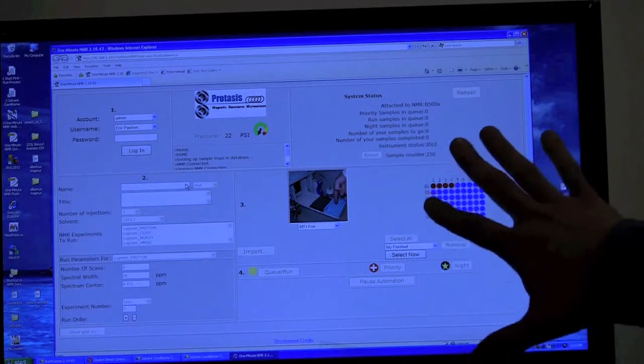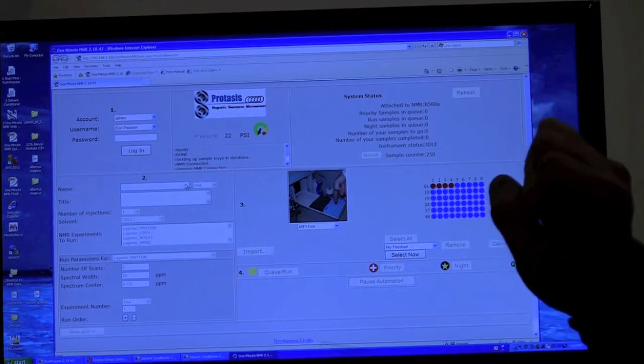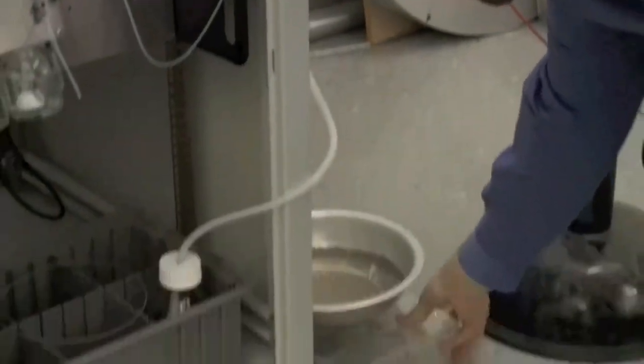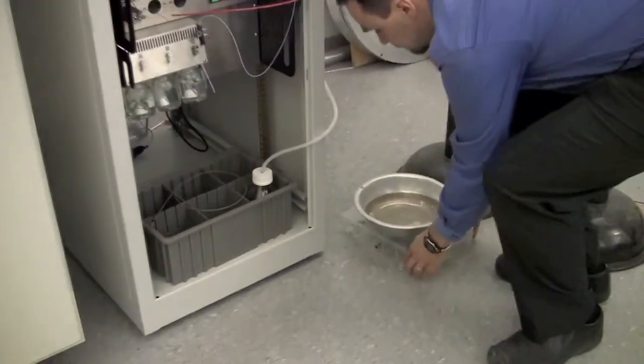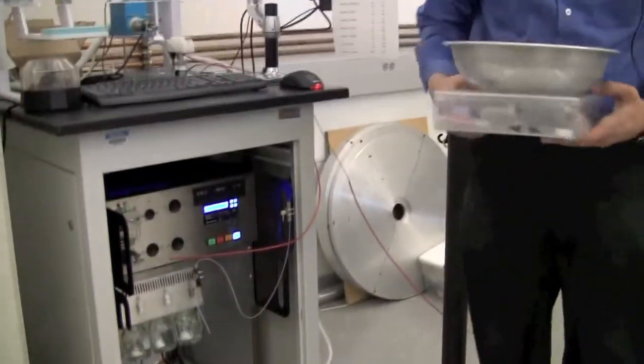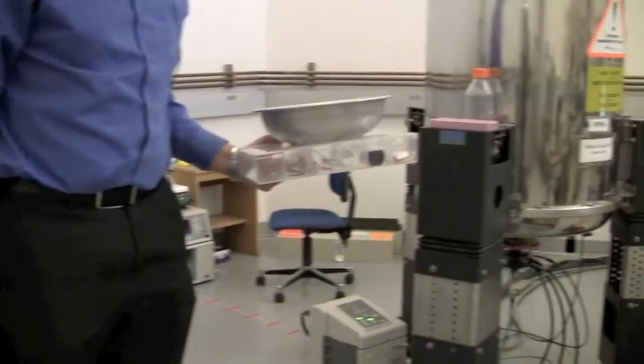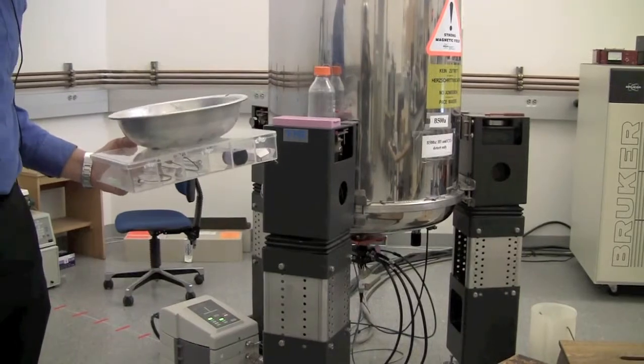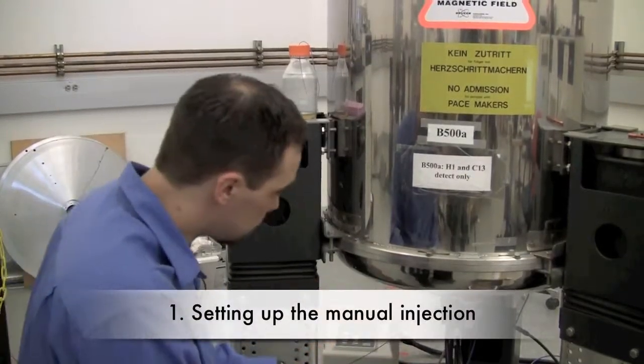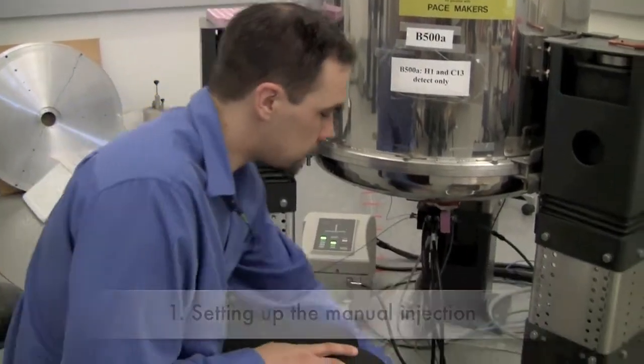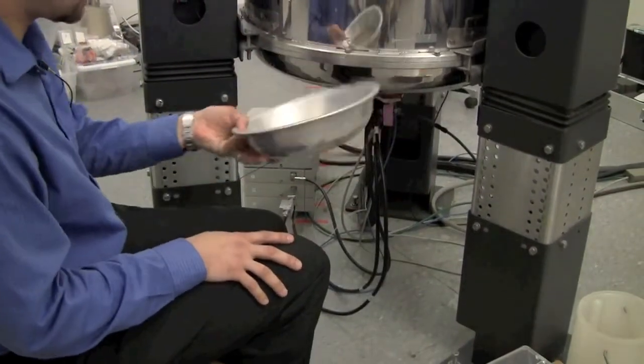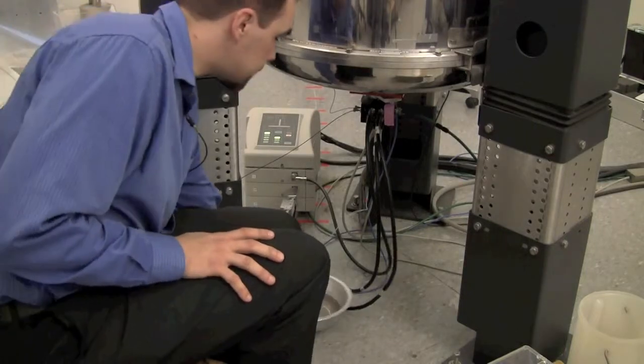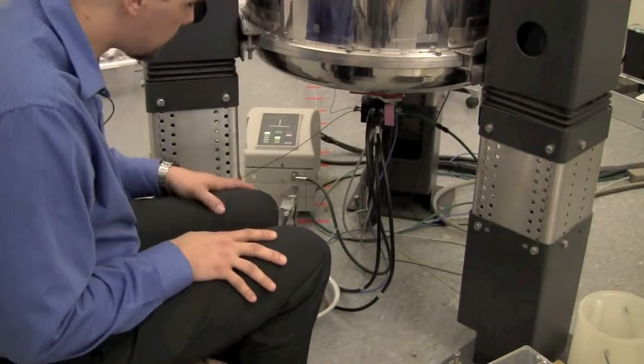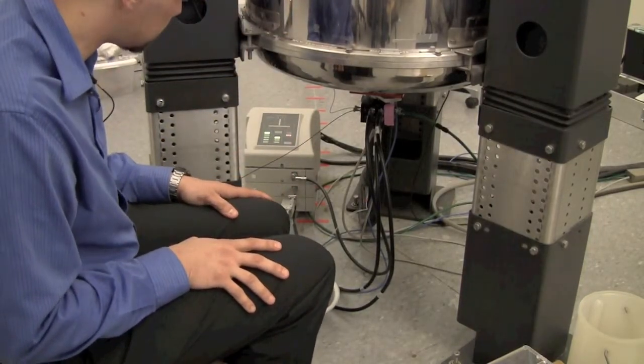In this case, everything's fine, nothing's running. So then we can get the kit for manual injection, which is down here. And we're going to take it over to the magnet and begin setting up for manual injection. Okay, so now we come over to the system and we're going to set up. The first thing is to put this bowl under here to collect any of the solvent that drips down as we're flushing various things out of the system.